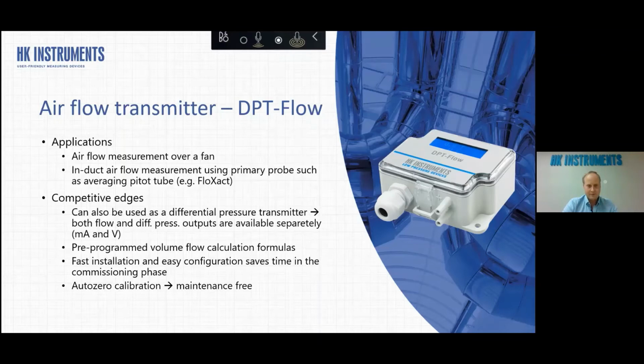And we have defined this kind of K value or flow formulas for different fan producers, such as Fläktwoods, we have Rosenberg, Nicotra, EBM-papst, and so on. So basically you need to know only which is the producer of the fan and what is the K factor. And it's like plug and play, so very easy and fast for the commissioning. And you can have this one also with the automatic 0-point calibration.